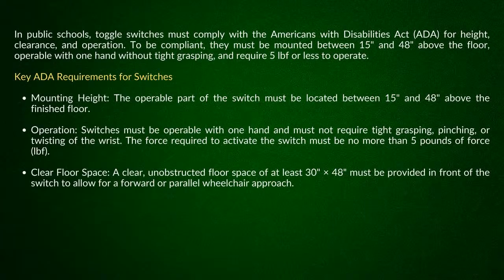I went and looked at the ADA requirements for public schools, and you do have to comply with ADA, including height clearance and operation. So for it to be compliant, these toggle switches need to be mounted between 15 and 48 inches above the floor, operable with one hand without tight grasping, and require 5 pounds or less to operate.